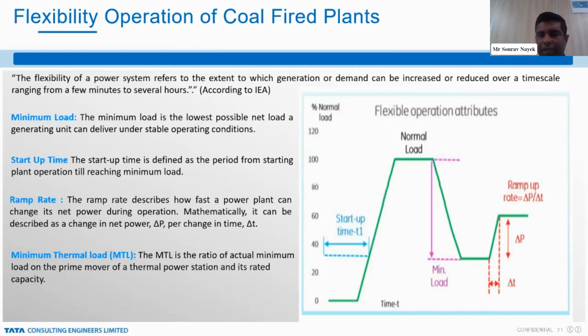If we see in the diagram, the green color is the first starting point, and then within the specified time we reach the normal load. So this is called the total startup time, from the zero level to reaching the normal load of the thermal power station. Now, the ramp rate, which will be ramp up or ramp down, we define with respect to megawatt per minute, and this is also reversible. Either we can ramp up or we can ramp down according to the demand from that plant. Now, minimum thermal load is the actual minimum load of the prime mover of a thermal power station, and the rated capacity. The ratio of these two is called the minimum thermal load.